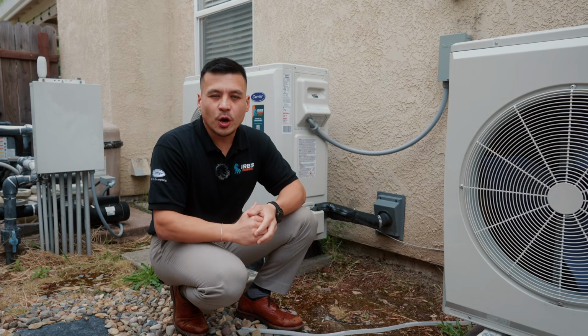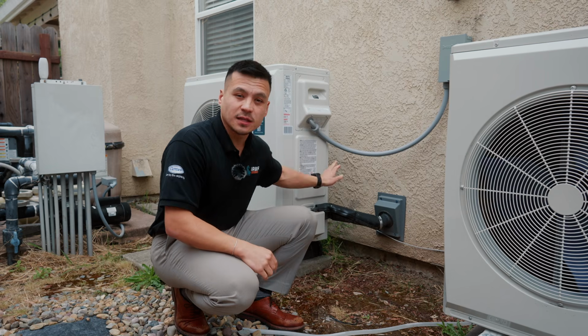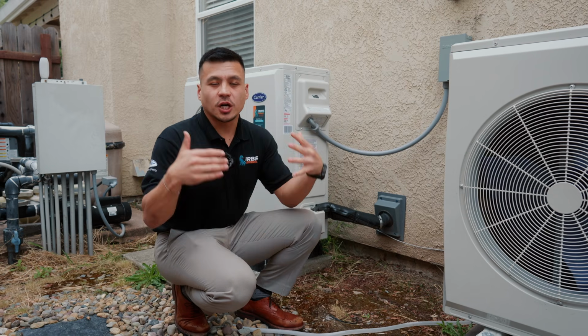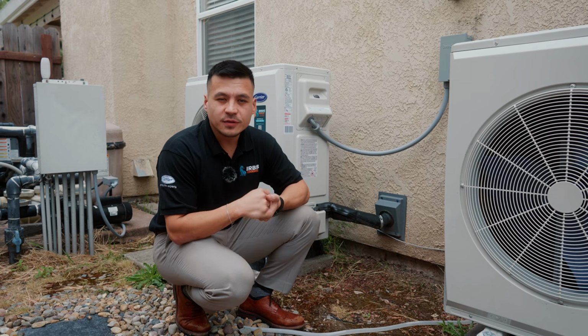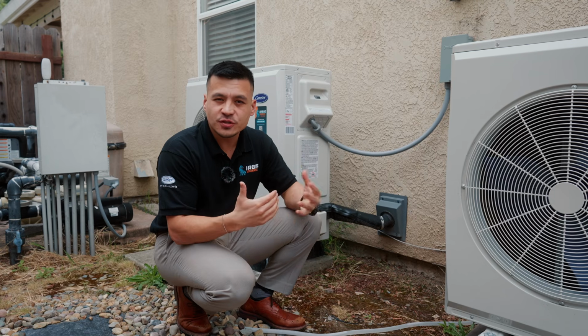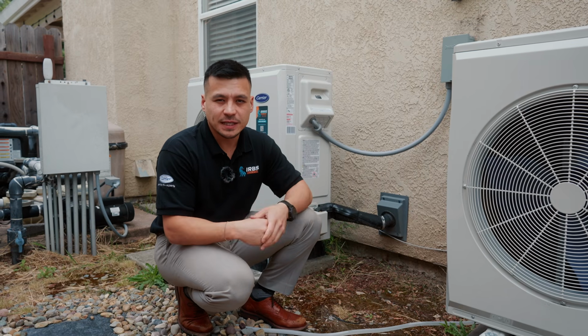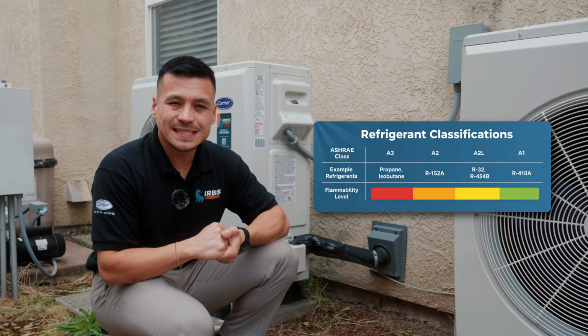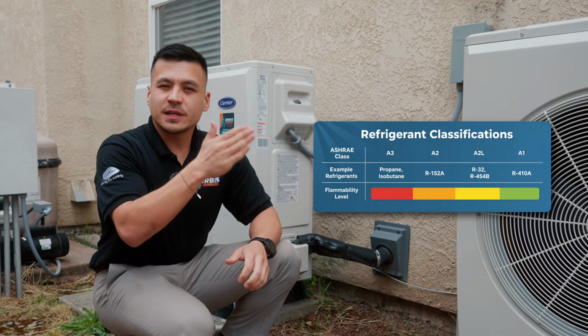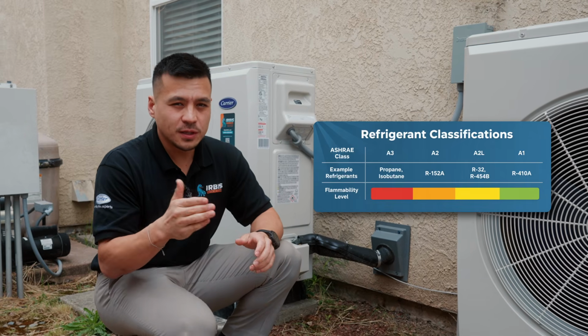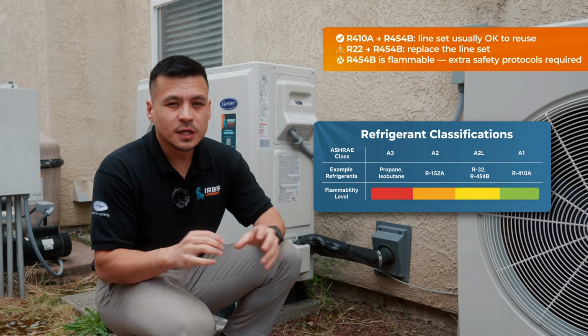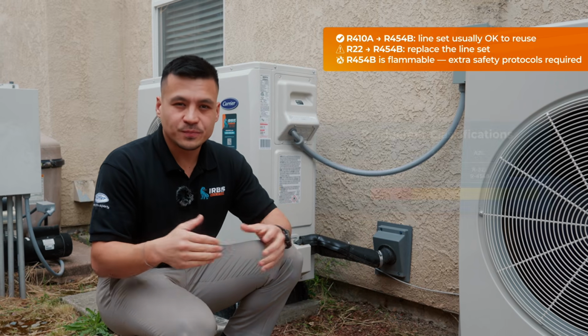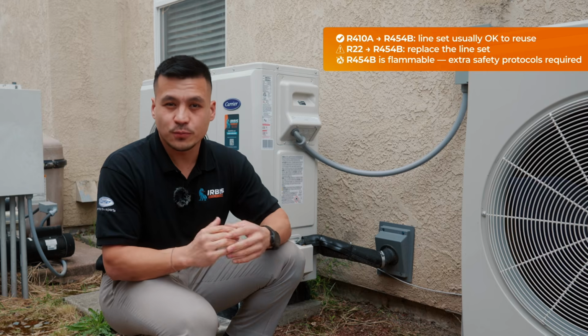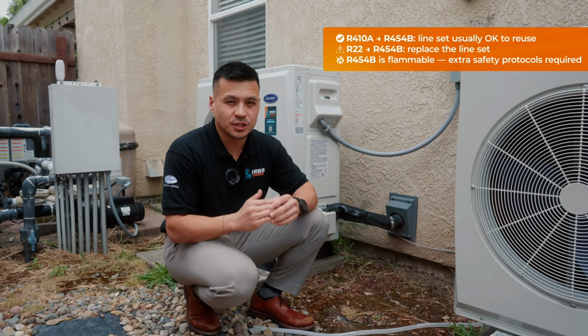The next important part is refrigerant and line sets. Starting 2025, the previous refrigerant R410A was phased out, and starting this year we use systems with the refrigerant named R454B, which is considered less harmful. However, it is flammable, so now we have extra safety protocols while performing installation services.